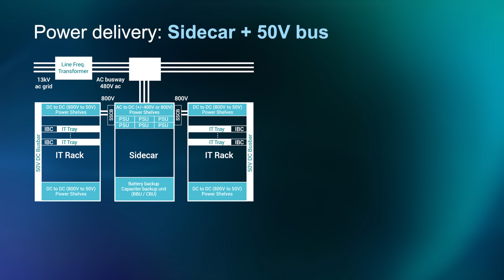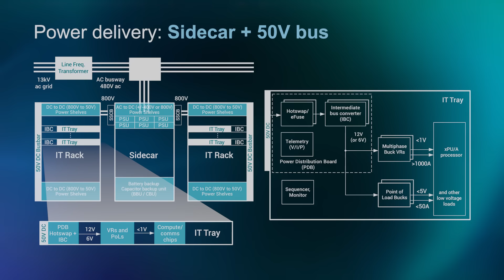Now, there may be multiple DC to DC power shelves in the rack that convert from 800 volts down to 50 volts. And like before, there's a 50 volt bus bar transmitting power up and down the rack. Now, the components in the IT tray remain essentially unchanged, as you can see in the diagram. The challenge is that even with liquid cooling applied to this 50 volt bus bar, the rack power will probably be limited to several hundred kilowatts of power. And with the pace of rising compute needs for AI and ML, even this architecture may not be able to cut it. So that leads us to the 800 volt bus rack.